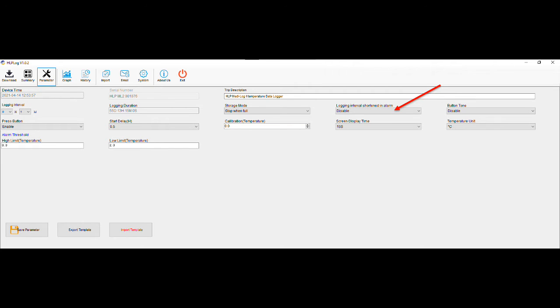Logging interval shortened, when enabled, will log the temperature every minute when the unit is in alarm stages. This feature is not recommended due to increased memory usage while alarmed and the risk of overwriting data if left for long periods of time. Button tone can be enabled or disabled to user preference. If enabled, a small tone will sound every time the center button is pressed. Press button should be left at enabled, as this will allow the center button to stop the unit as well as switch between the available screens.